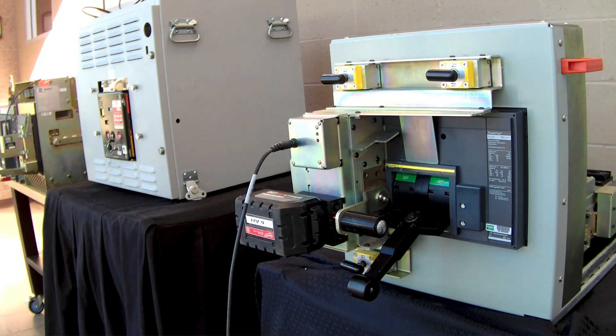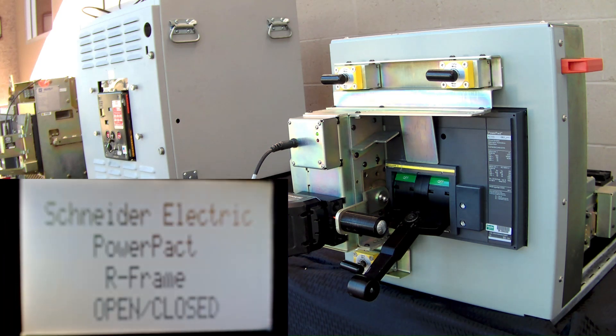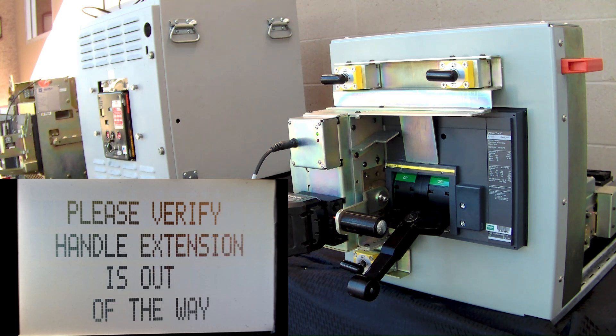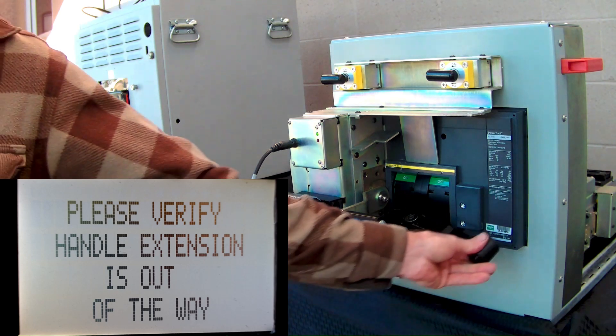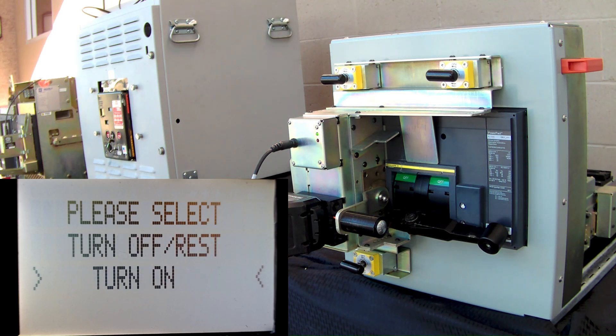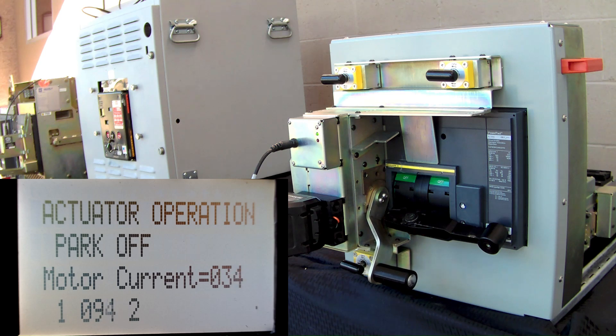This is a Schneider Electric PowerPact R-Frame. With this particular breaker we need to drive the actuator to the park position, and then we will drive to the correct location to grab the handle. Please verify the handle extension is out of the way. We want to go from off to on, so we will push the up button to turn on. The bracket is parking low enough to grab the handle.